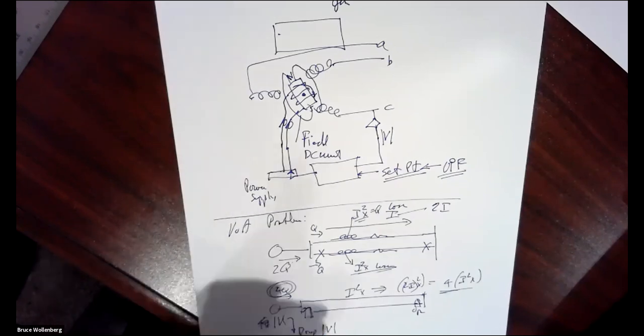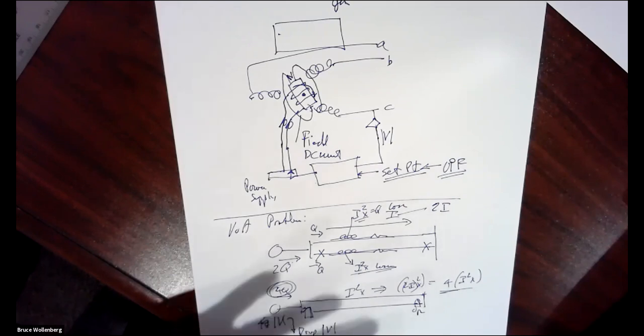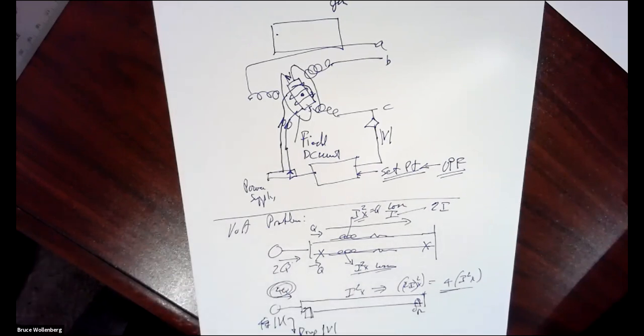So you get an insufficient amount of Q into the system, and then the whole system begins to go down. And typically you can get into a voltage collapse situation when you don't have enough reactive source. The chief source of reactive power are generators. You can then use capacitors, or you can use static VAR compensators, which is a fancy way to say power electronic units that can supply reactive power, and supply it without cost. It doesn't cost anything to operate it. Well, it costs a tiny bit, but it's not like having to have a generator online.